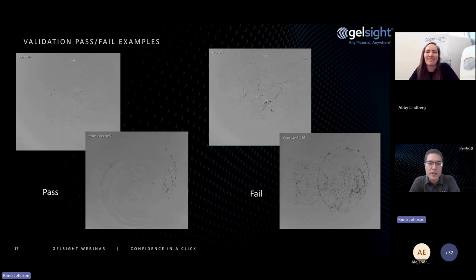Yeah, so as we discussed at the beginning of this presentation, our system is calibrated to the unique reflectance properties of the gel. So if the image is seeing black pixels because there are holes in the membrane, or white pixels because you're getting reflections from the part underneath, you're no longer satisfying the unique properties of a GelSight system. So the gel needs to be replaced to get you back into the measurements with GelSight technology.